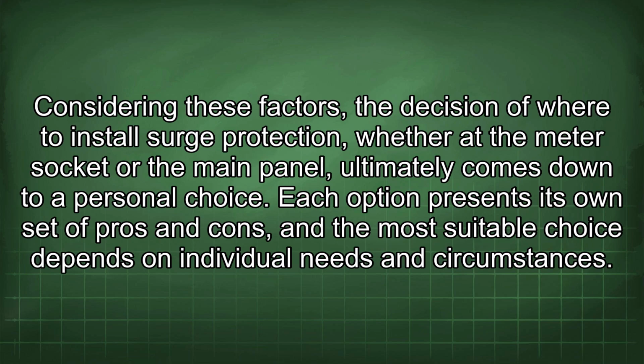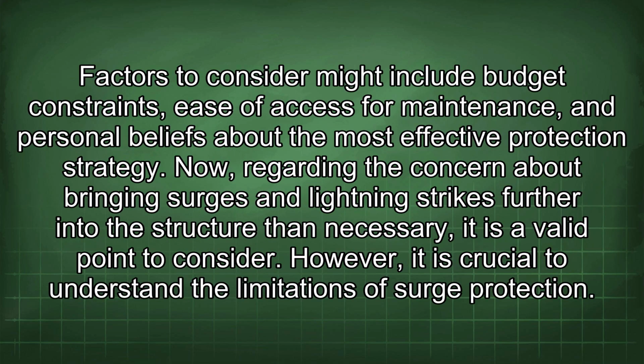Considering these factors, the decision of where to install surge protection, whether at the meter socket or the main panel, ultimately comes down to a personal choice. Each option presents its own set of pros and cons, and the most suitable choice depends on individual needs and circumstances. Factors to consider might include budget constraints, ease of access for maintenance, and personal beliefs about the most effective protection strategy. Now, regarding the concern about bringing surges and lightning strikes further into the structure than necessary, it is a valid point to consider.